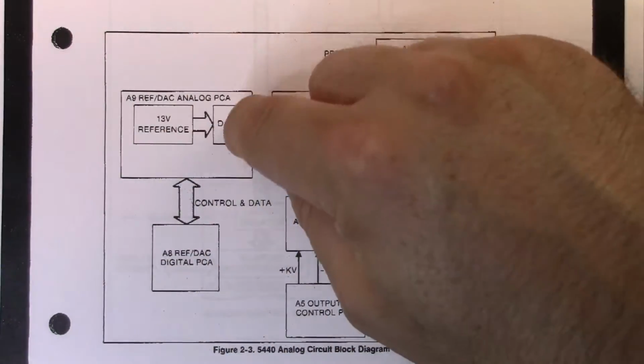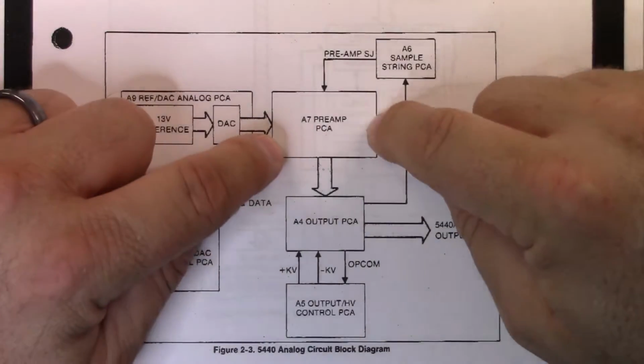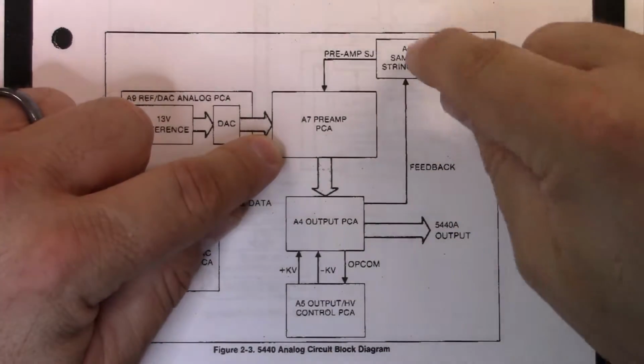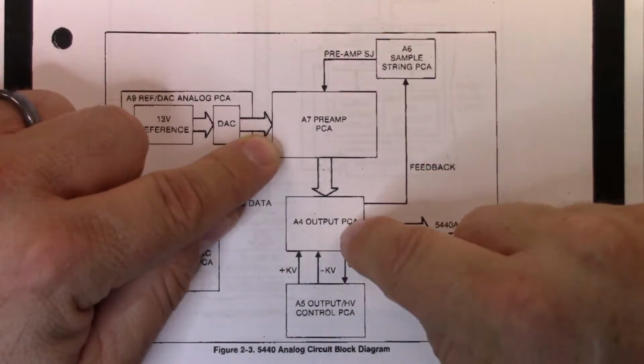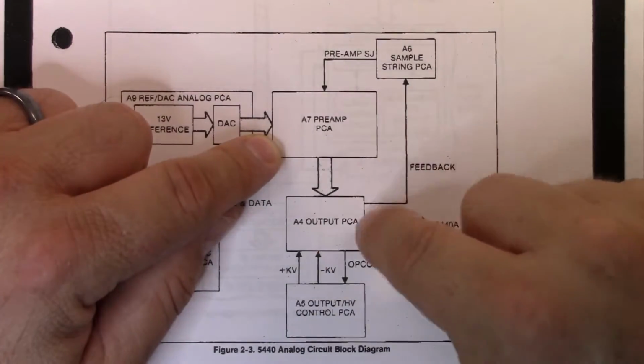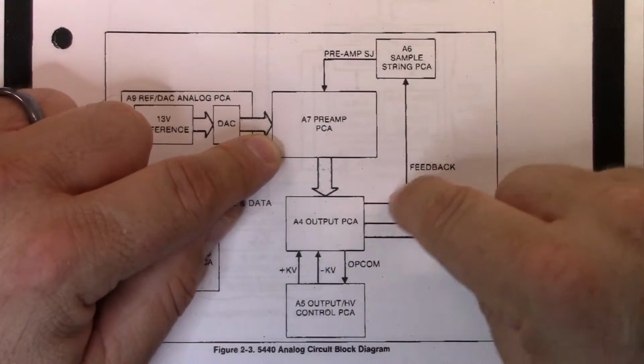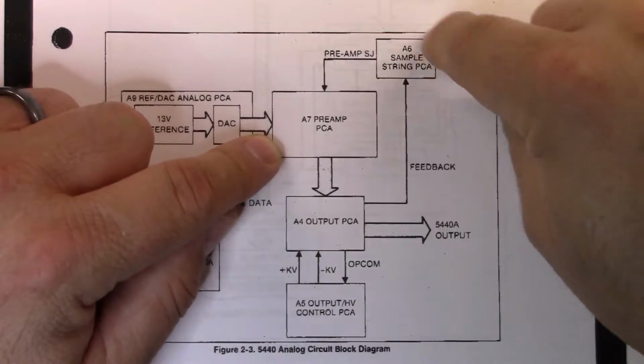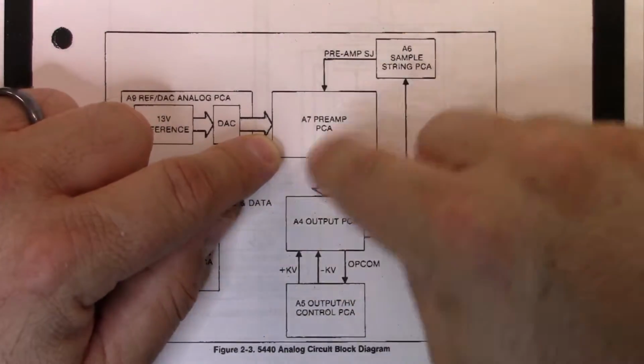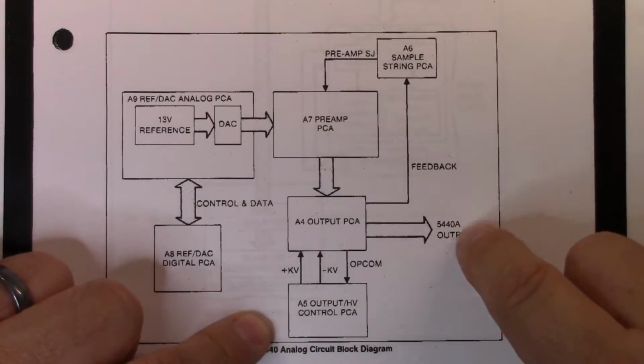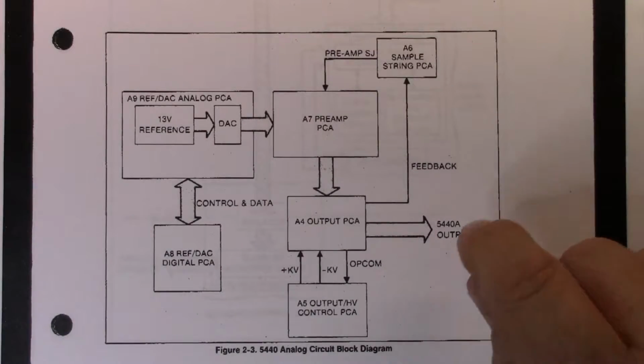So basically what happens is you set your value here, and an analog value is sent out into the preamp. The feedback loop goes through the output control set, the output PCB assembly, through the feedback, through the sample string, back into the preamp, and gets controlled. Finally it's put out on the output of the device.